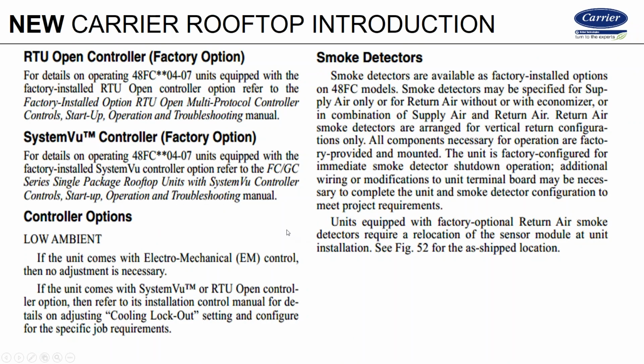And that's about it. I don't know if you had a handout, I think we didn't do that, but the unit is capable of running RTU Open. It's a multi-protocol board that can speak BACnet, LonWorks, Modbus, it speaks all 4 languages. And basically your front-end system is going to talk to the RTU Open controller, and the RTU Open controller is going to put out commands for Y1, Y2, economizer position, take feedbacks like supply air temperature and things like that. So it's an integration board or multi-protocol board, if you will. Matter of fact, we used to call it RTU MP, MP standing for multi-protocol.